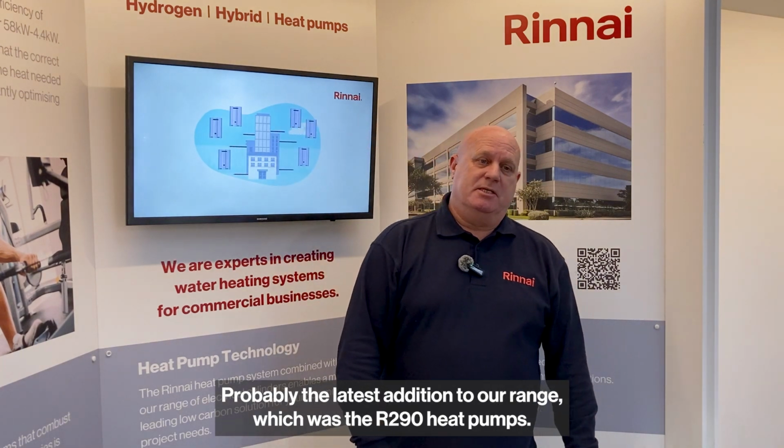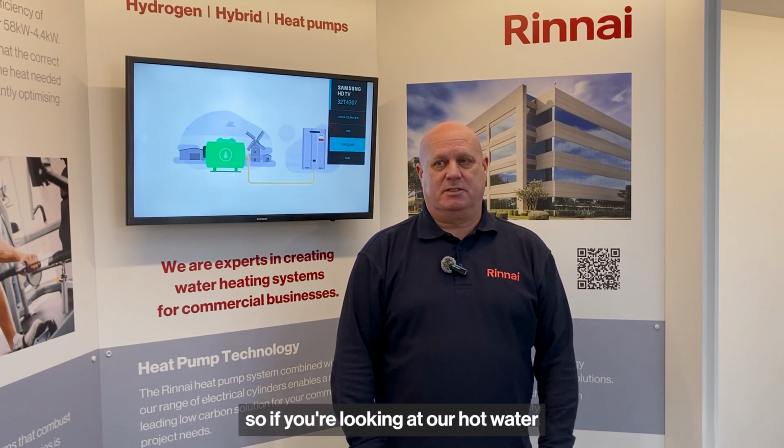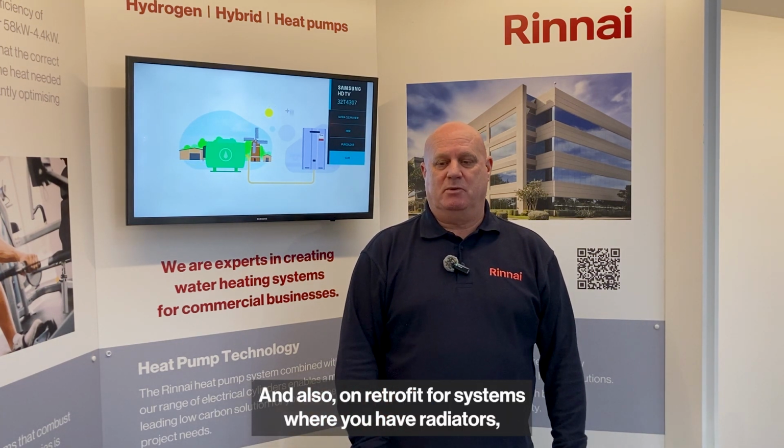Probably the latest addition to our range was the R290 heat pumps. We were supplying heat pumps for a year or two before that, but they were R32, which is a lower temperature, 55 degrees top end. The R290, we can get up to 75 degrees. So if you're looking at a hot water system, you won't have to have any immersion heaters to lift the temperature. And also on retrofit for systems where you have radiators, it's almost a replacement for any boiler that's already in there, because it can go in and do the same sort of temperatures.